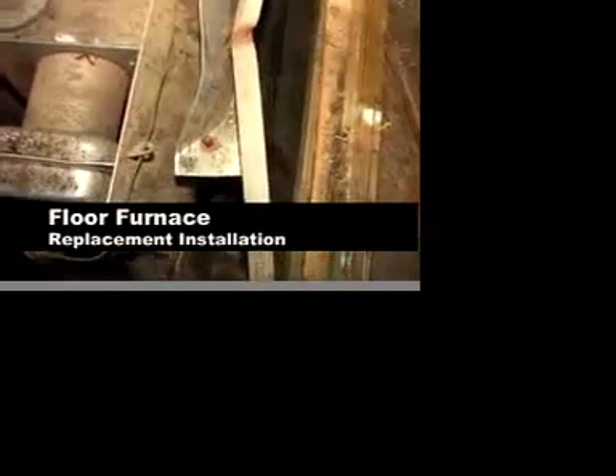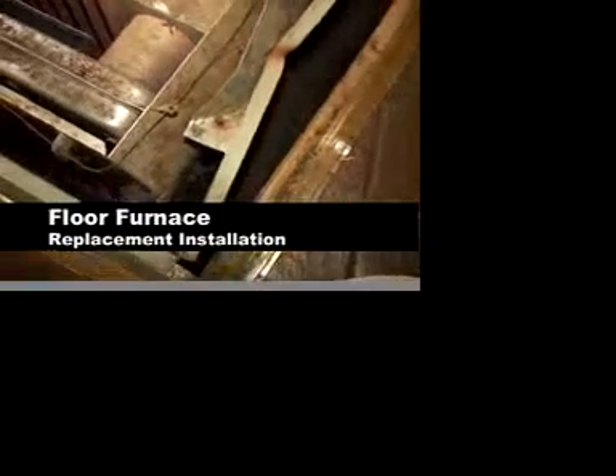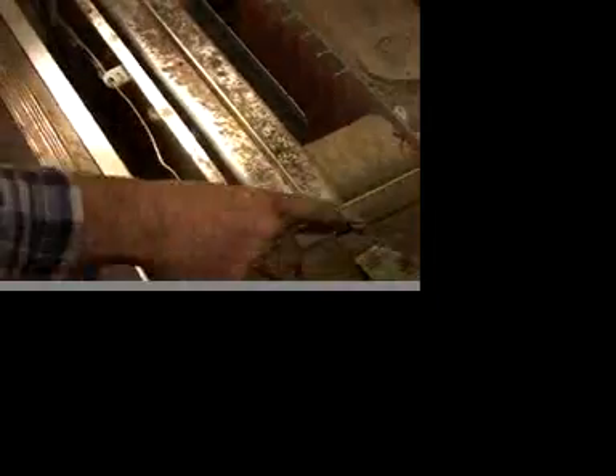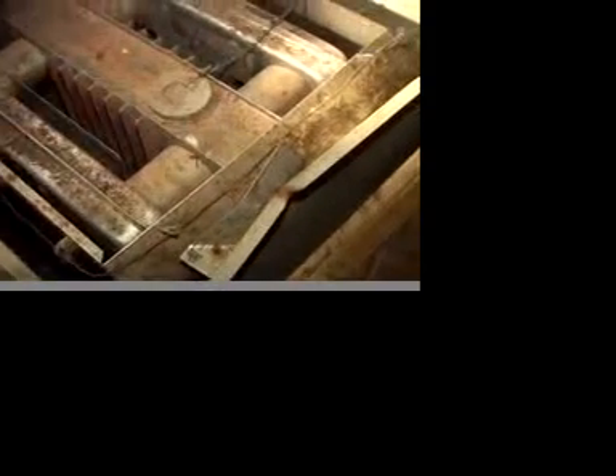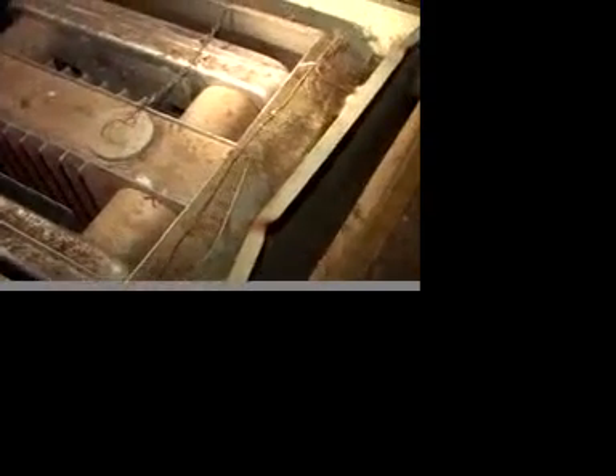In the process of replacing this 1940s style floor furnace, we notice that even as old as it is, it has some of the safety equipment that the new furnace has. This is a thermostatic wire that goes over here to a thermostatic switch, and that switch will turn the furnace off if this gets above 300 degrees.